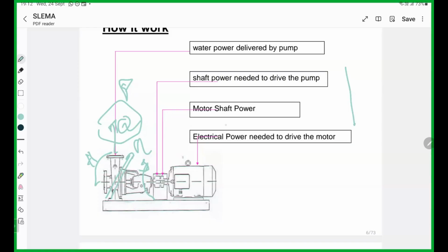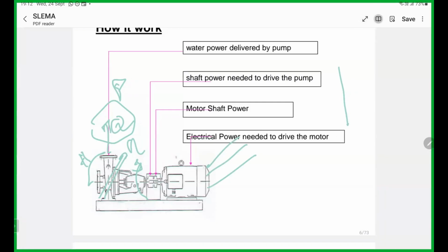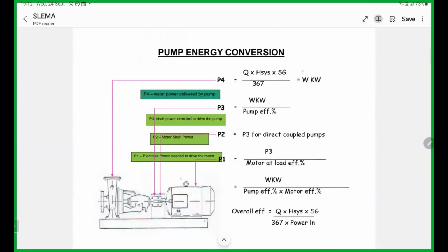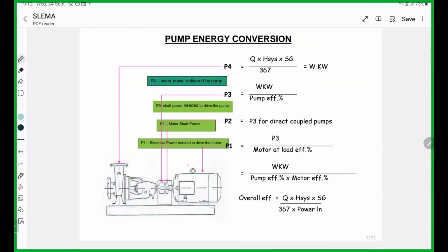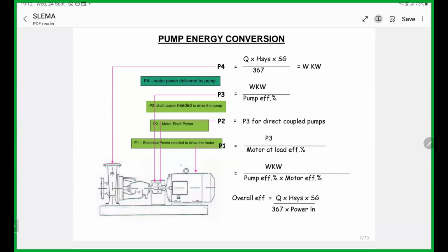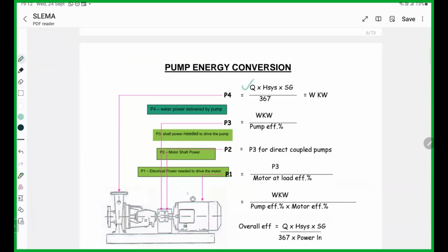Then we have motor shaft coupling. Then we have shaft power. Then electrical power, electrical input. Then the general idea is this, that is how the pump works, right? If you come to that energy conversion, then this equation is important. Water power out is the flow rate, and the flow rate should be in cubic meter per hour. Then specific gravity for water is 1. Then H system head is in meter. Then the P for this water power output, we can calculate by using this equation.